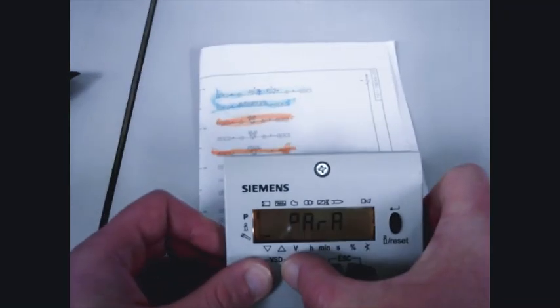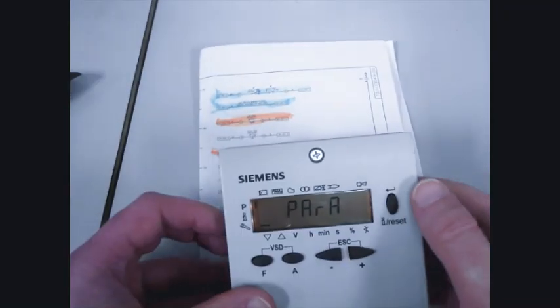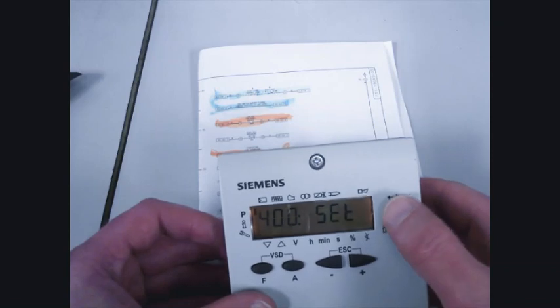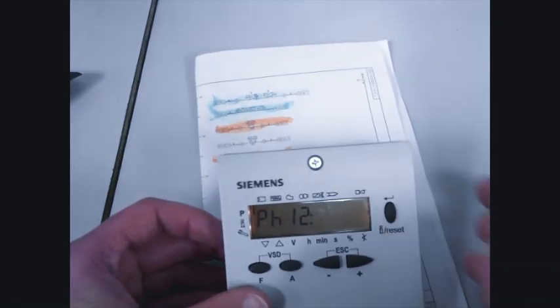Get back into commissioning. Enter, enter. We turn the burner switch on. The blower motor comes on, combustion air is made, and low gas pressure is good. We start our purge countdown of 30 seconds.